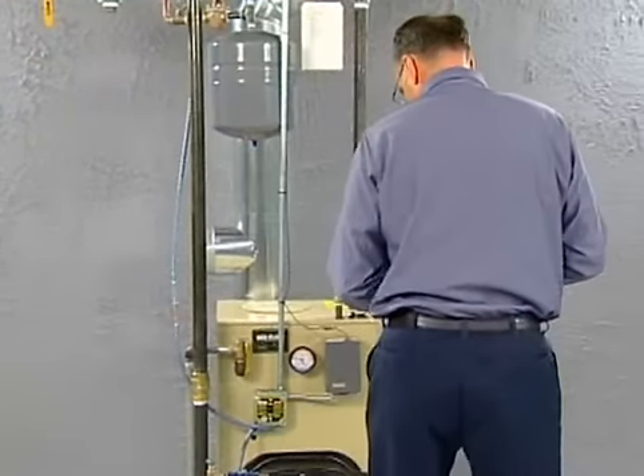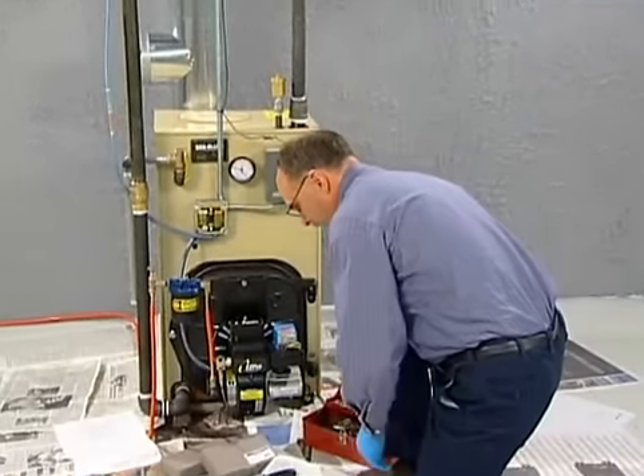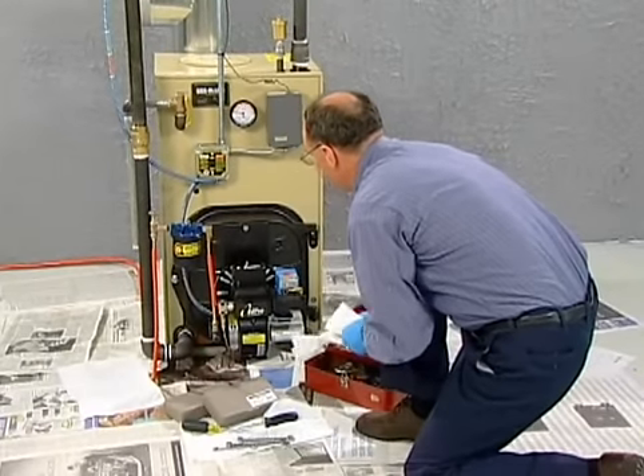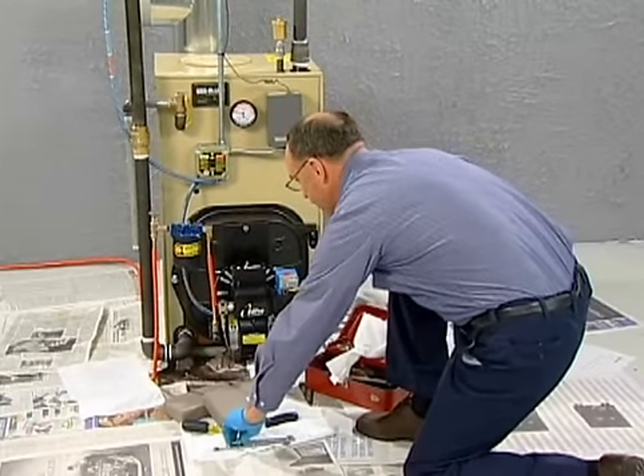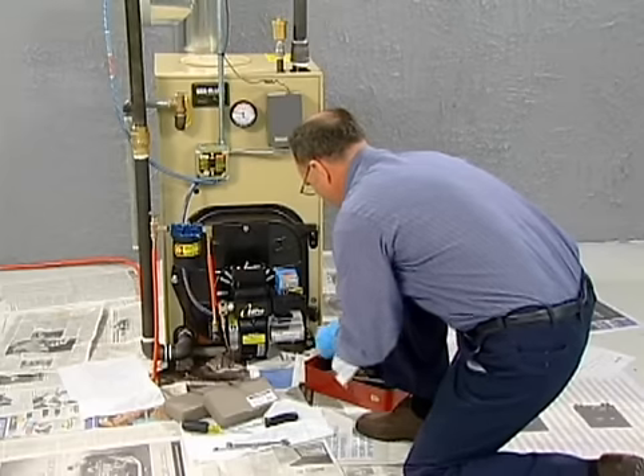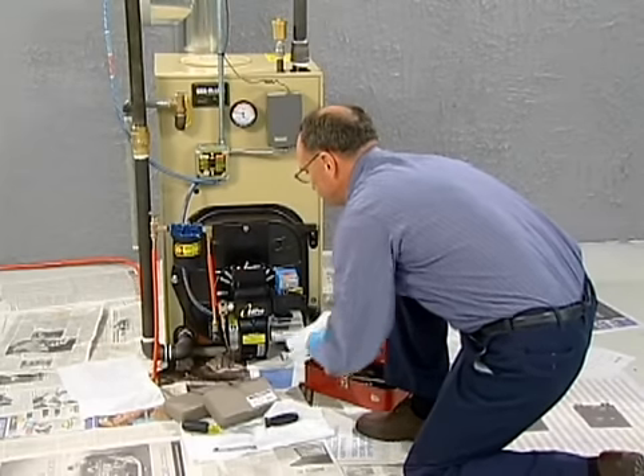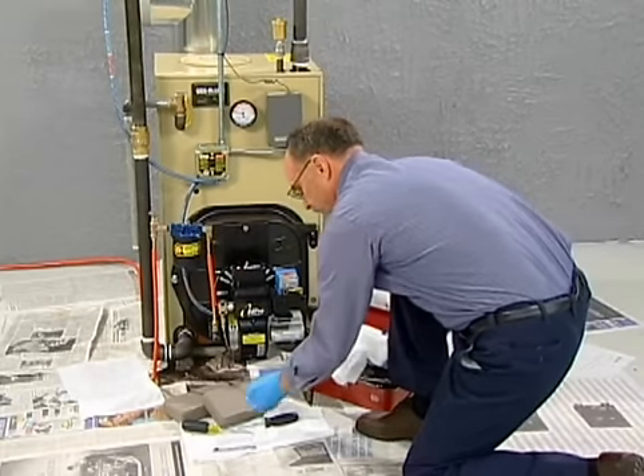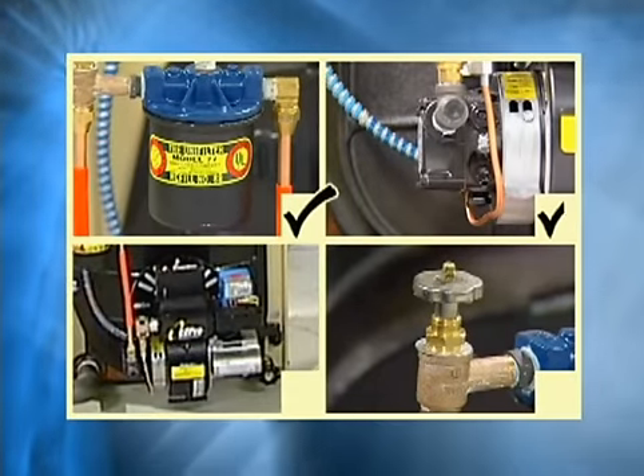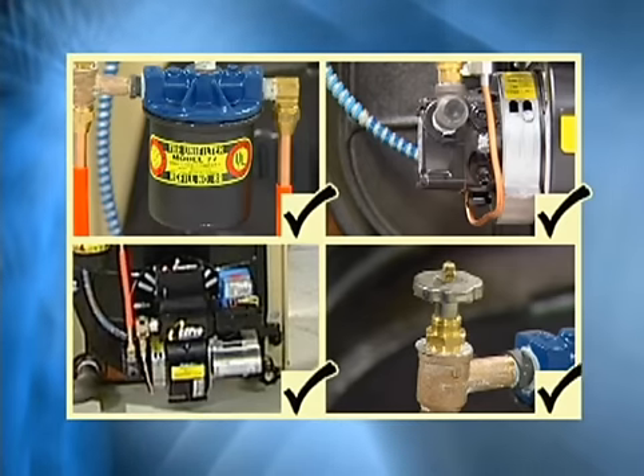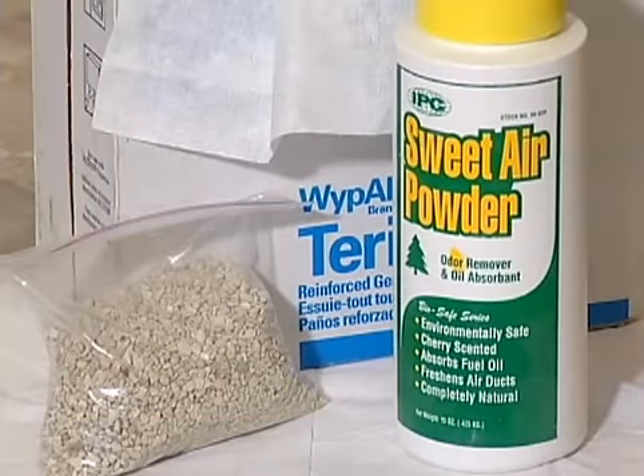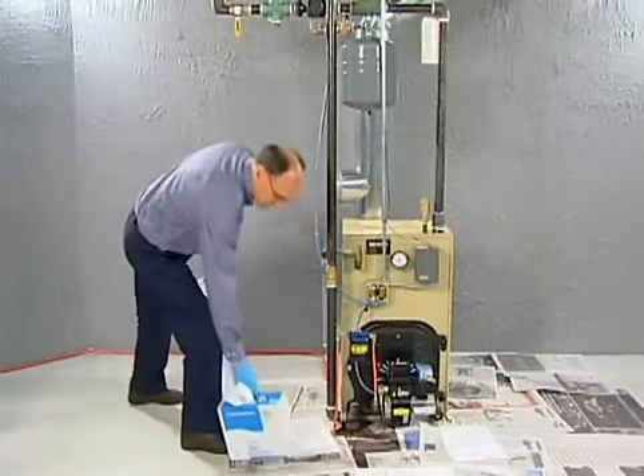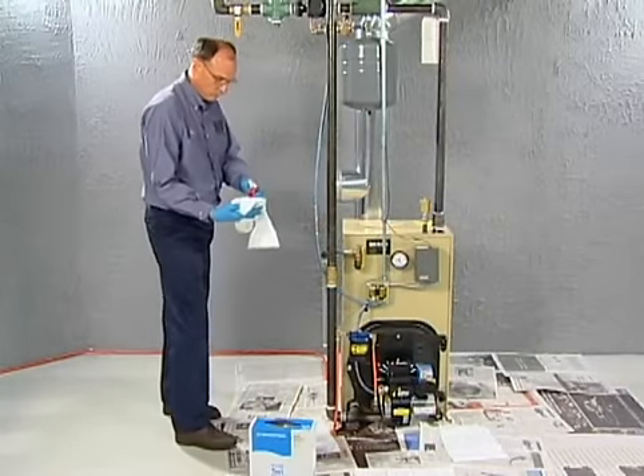Once you're satisfied that everything is working properly, double-check to be sure that you removed any jumpers you may have used, gather your tools, and check the area one last time. Pay particular attention to oil odors and to potential sources of oil leaks, such as the filter canister, pump, burner housing, and oil valve stem. Don't just wipe spills up. Use an absorbent and deodorizer. Always leave the area cleaner than you found it.